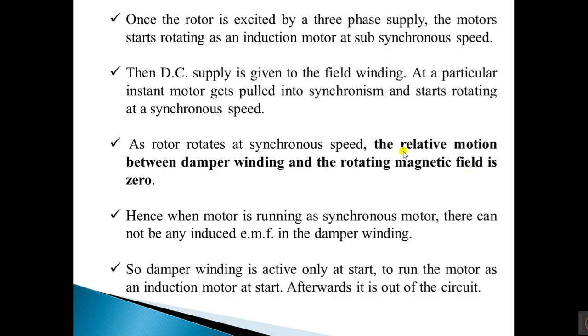Once the stator is excited by a three-phase supply, the motor starts rotating as an induction motor at sub-synchronous speed. The DC supply is then given to the field winding. At a particular instant, the motor gets pulled into synchronism and starts rotating at synchronous speed. Now the stator field and rotor are rotating at the same speed.